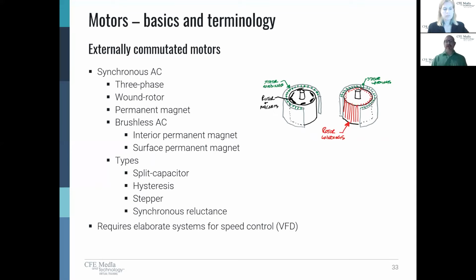The only way to change the speed, of course, is to use a VFD. I have to vary the frequency in order to change the speed of a synchronous motor. In addition, you can either do magnets on the inside or you can do DC wound coils. And the DC wound coils look kind of similar to what I showed you before with ECM, where we're running DC current and we're generating a magnetic field.